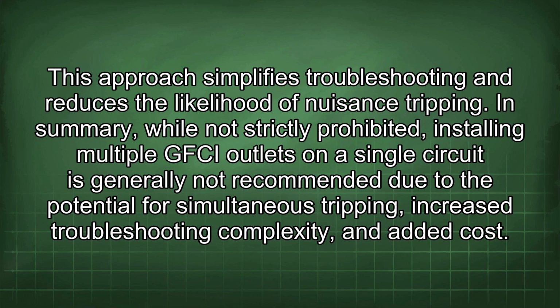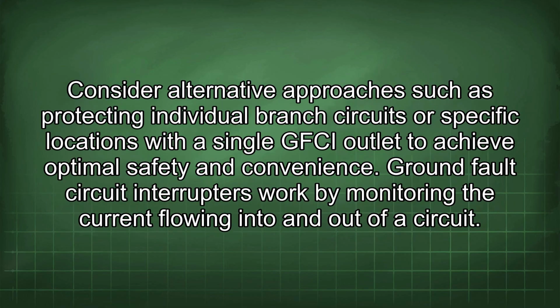In summary, while not strictly prohibited, installing multiple GFCI outlets on a single circuit is generally not recommended due to the potential for simultaneous tripping, increased troubleshooting complexity, and added cost. Consider alternative approaches such as protecting individual branch circuits or specific locations with a single GFCI outlet to achieve optimal safety and convenience.